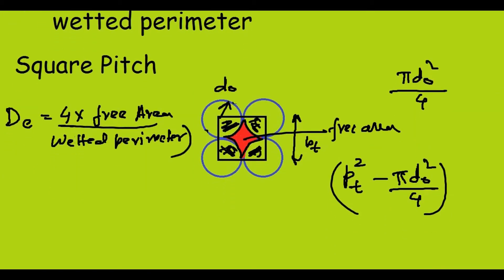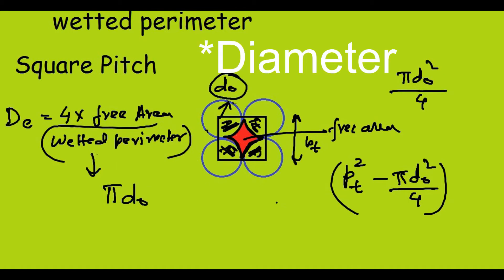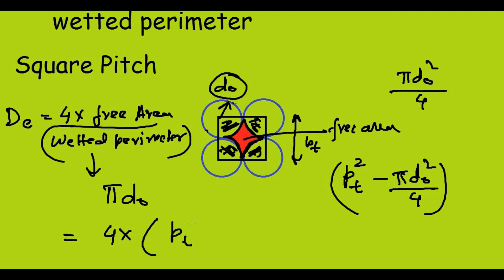Now I have the free area. All I need is the wetted perimeter, which is the perimeter of the black shaded portion — the rim of this red shaded region. I have 4 quarter circles, which add up to one full circumference, so the wetted perimeter equals πDO. This gives the equivalent diameter for square pitch as: De = 4(Pt² − πDO²/4) / (πDO).